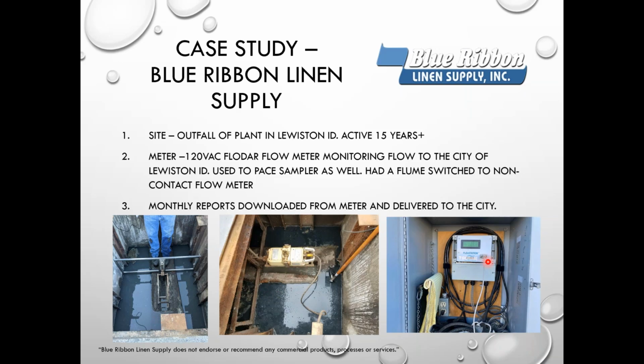It's a 120 volt AC unit. It also has a contact closure that activates their sampler. So when the city comes out, they plug into the flow meter, and it helps give them a flow paced sample. They basically just plug into it, and they take a monthly report, which they download from the instrument, and they hand it over to the city.